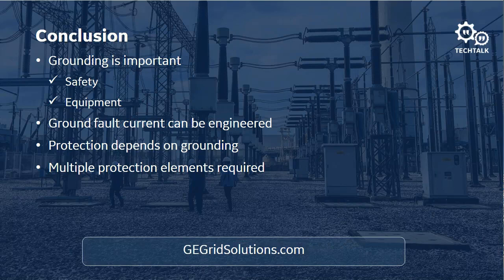If I can take one more question. Hybrid grounding seems to be the best protection. Why would we use any other method? And he says cost. And of course, cost is one of the most important factors. I personally have never seen a hybrid grounded method being used in most of my travels or my career so far. I could be wrong, and I believe it's because of the cost, because you need that extra switching device, which needs to be a high-speed device. And then you need the resistor to go along with that, so that becomes expensive. Then you also need the high impedance grounding transformer. So the cost associated with that method is going to be significant.